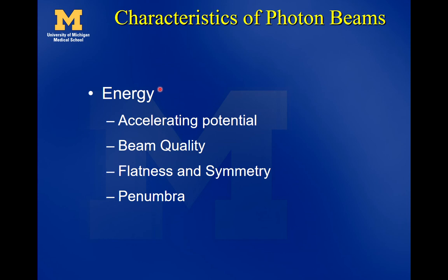All of these characteristics are used to describe our photon beams used for treating patients. One of the most important things about the x-ray beam is the accelerating potential — 6-MV versus 16-MV accelerating potential will produce very different x-ray beams, so it's critical to know which energy we're treating with. This also relates to beam quality, a jargon term that tells us how high or low energy the x-rays are in the spectrum for different MV x-ray beams.